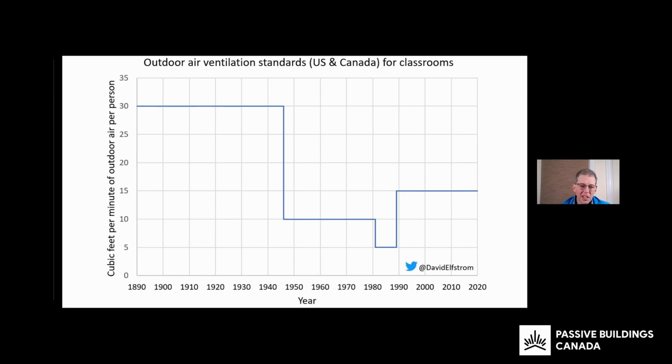So when a school district says it's operating as designed, you can ask them which design year. Was it 1985? Because if it is, then we want to investigate whether it has been retrofitted since then to have the increased levels that are acceptable today. Pandemic guidance for schools is mostly from Harvard School of Public Health, and they're going back to basically double, so 30 CFM per person, working out to an air change rate of 6 air changes per hour in a classroom.